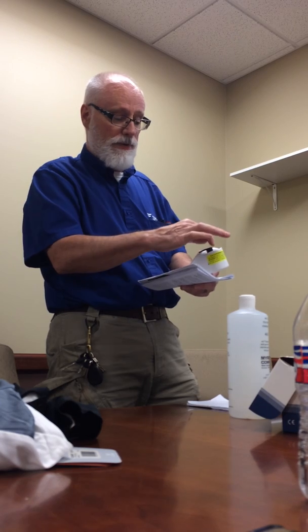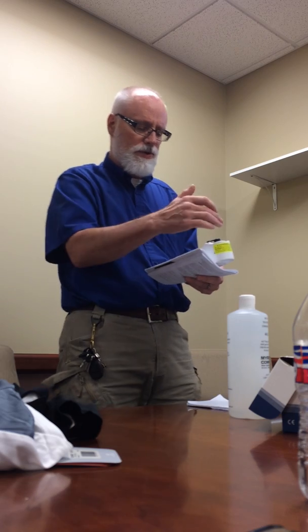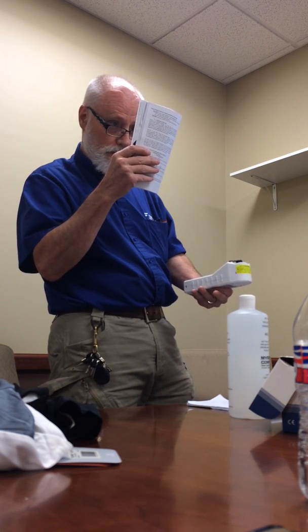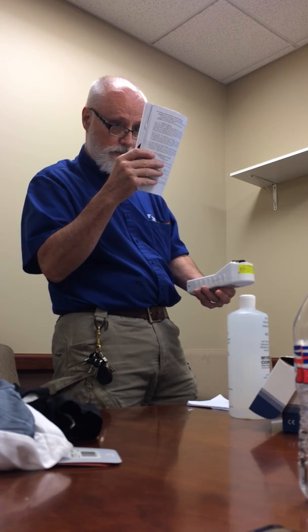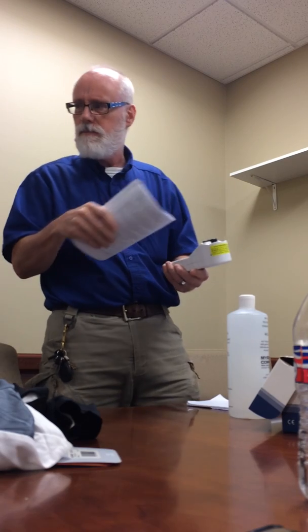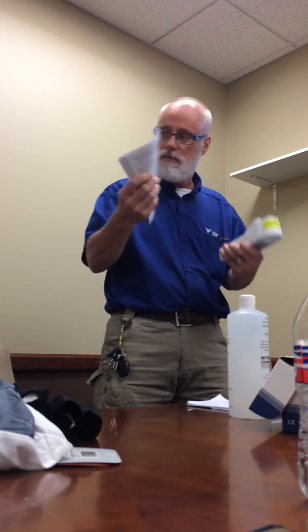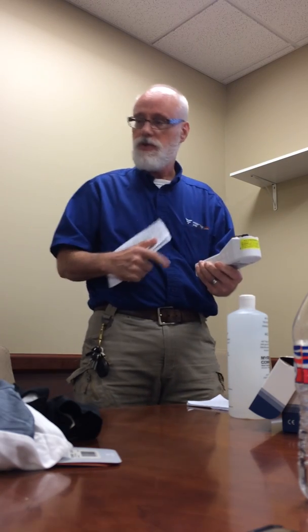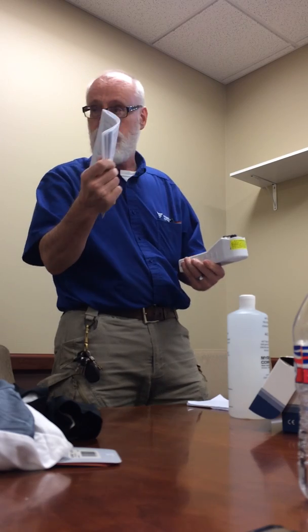So you're filling both of these reservoirs up 3 times, rinsing them out, and then that 4th time that the solution's in both sides, you're going to hit TDS. You look and see where you fall. It should be between 3030 and 2970. How many sides are you filling? Both sides, rinsing them out 3 times. And then the 4th fill, then you hit TDS, see what it reads. And if it's in range, they don't have to calibrate it.